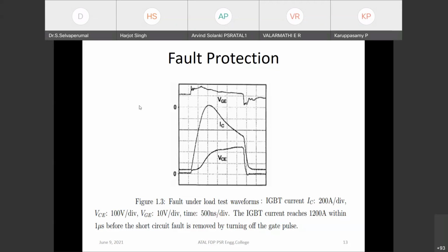So the IGBT current reaches 1200 ampere within 1 microsecond before the short circuit fault is removed by turning off the gate pulse. So di by dt tracking capability of the sensors must be sufficiently high to track the short circuit current. Shunt resistors, current transformers, and Hall effect current sensors are usually employed in short circuit protection of power electronic circuits. So nowadays, some IGBTs have an inbuilt sense resistor in the output part to be used for overcurrent and short circuit protection. Next slide.